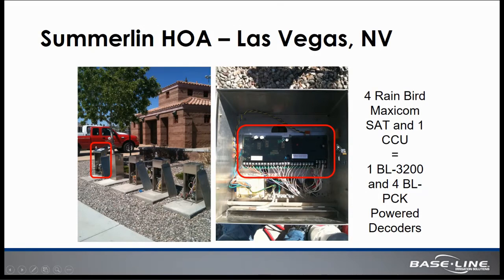those pedestals. The existing valve wire was all wired up to those terminal posts, and then the wire that linked them together was the existing PE89 cable that ran from pedestal to pedestal back to the CCU. We used that as a wire path to consolidate all 4 of those controllers into one interface. So now that one controller operates 176 zones on this one park site.